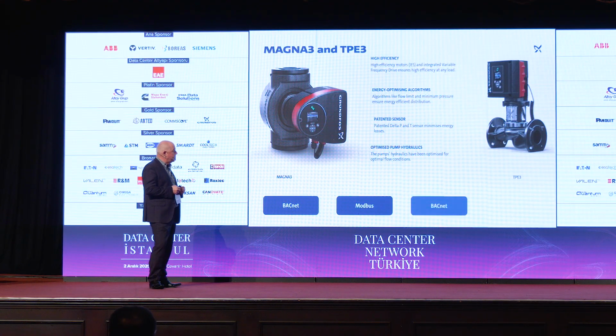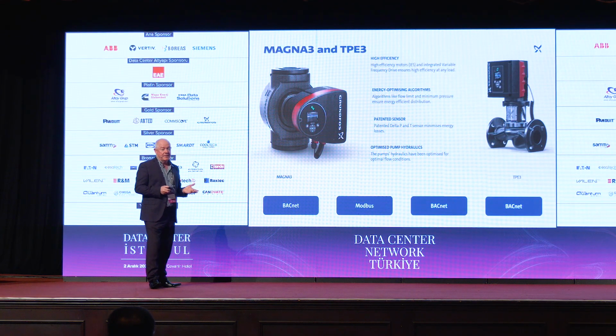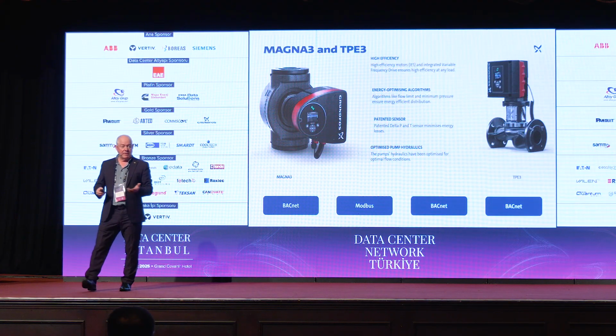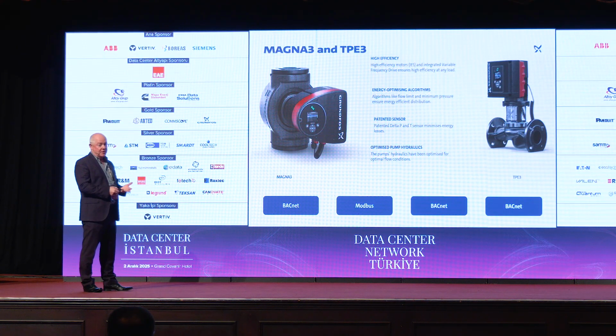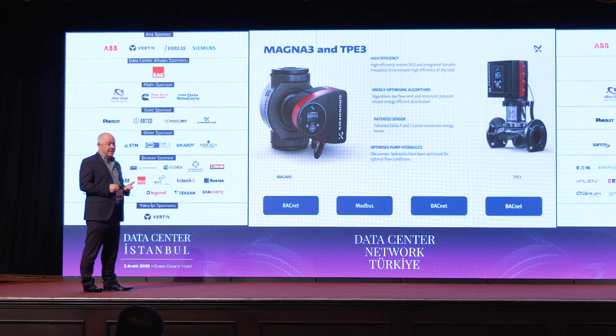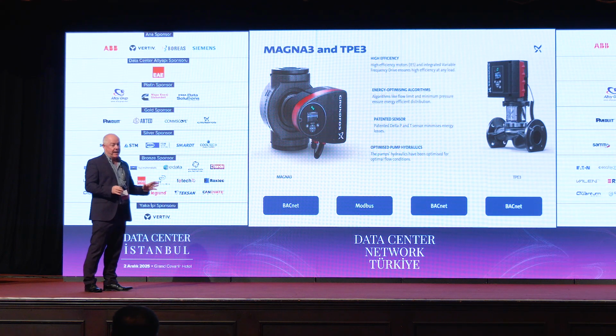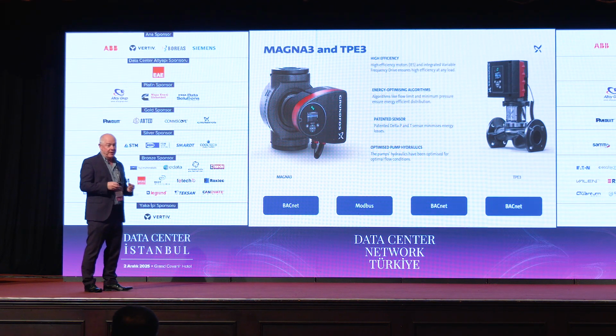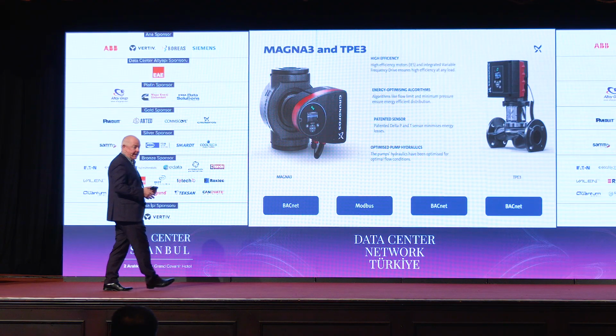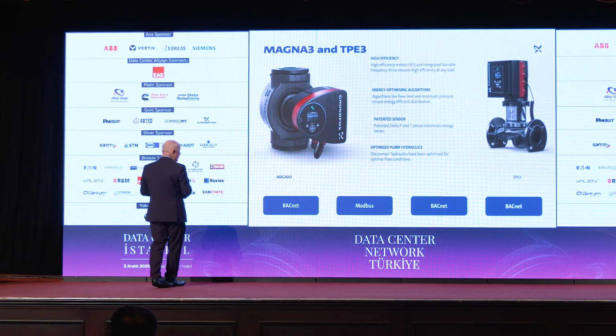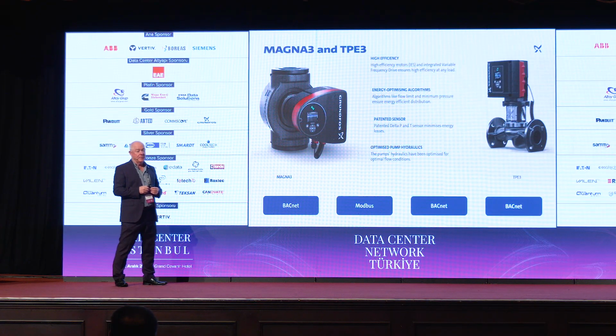And if we have a look at the products that are being used, they're standard Grundfos products, which are available in the market all the time. The controllers are standard, the pumps are standard, the sensors are standard, and the communication cards are pretty standard as well. So nothing here is unique. It's not something that cannot be picked up through standard distribution. And we can make the pump skids on the primary side, we can modularize them and have them come in as skids and kits and whatever. So it's all pretty standard Grundfos product, just used in a slightly different way in how we control it.